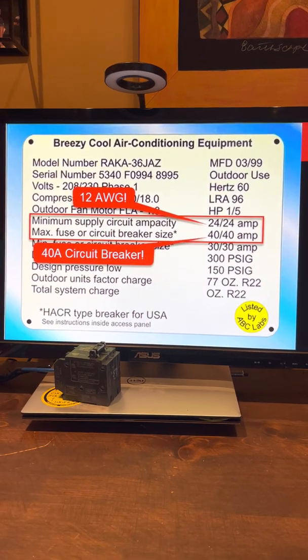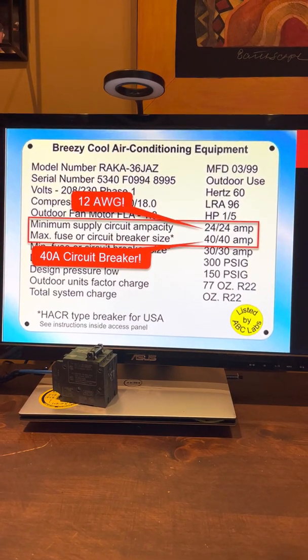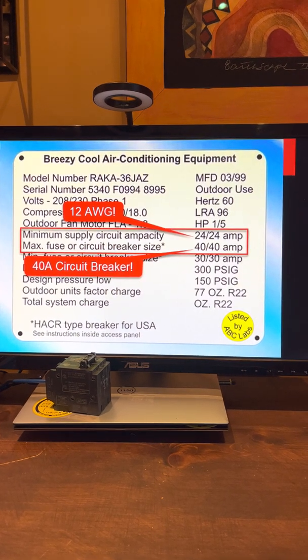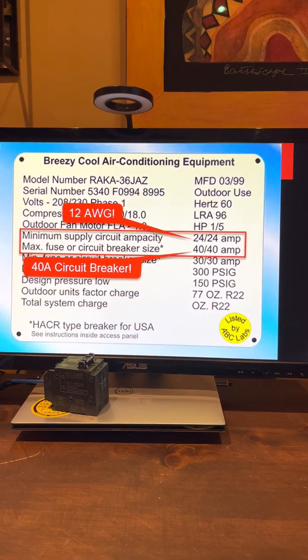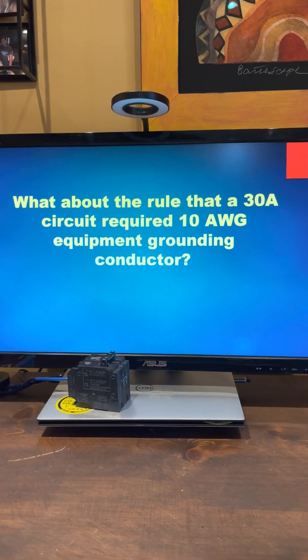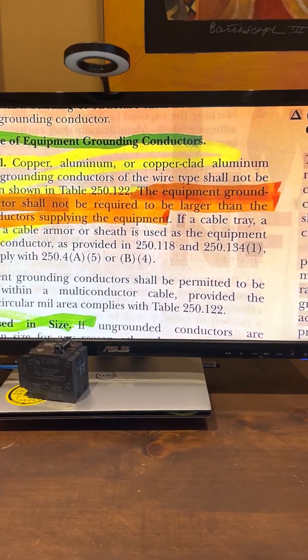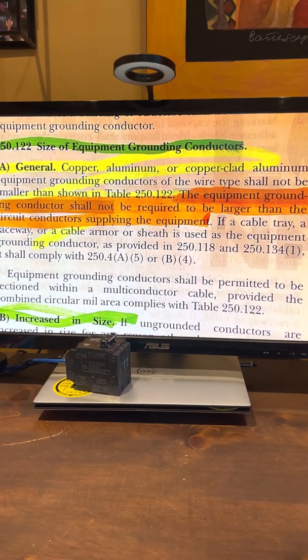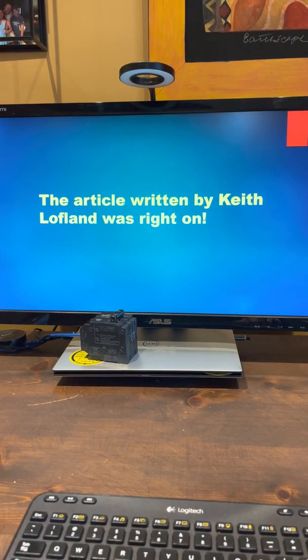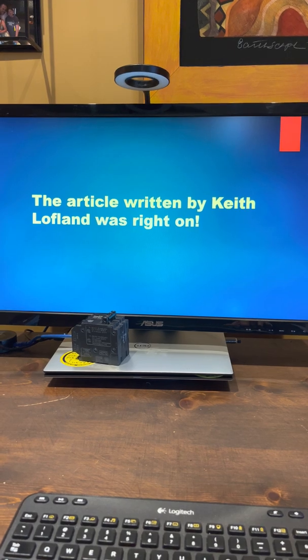You might worry that the wire will burn up or cause a fire. The National Electric Code has been around 125 years — they already know that a 12-gauge wire will comfortably withstand a short-circuit event of maybe 300 milliseconds of a second. It's fine. The air conditioning unit itself has individual overload protection; this breaker is short-circuit protection. What about the rule that a 30-amp circuit requires a 10-gauge equipment grounding conductor? Per 250.122A, the equipment grounding conductor shall not be required to be larger than the circuit conductor. So: 12-gauge circuit conductors, 12-gauge equipment grounding conductor, 40-amp breaker. The article by Keith Lofland was right on. If you're a dinosaur, don't bother telling me Keith is wrong — but if you learned something here, you're not a dinosaur.